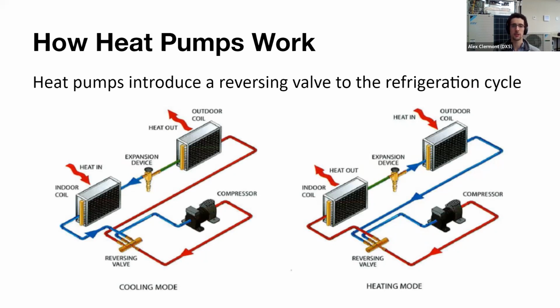Now, how do you actually reverse this cycle? You don't just turn flow the other way. The flow always goes through the compressor in the same direction. You actually have this device here called the reversing valve. And in the summer, you send discharge gas off the compressor to the condenser outdoors. This real hot gas can actually get cooled by warm-ish air outdoors. In the wintertime, you actually send the discharge gas right to the indoor units, which actually becomes the condenser coil.